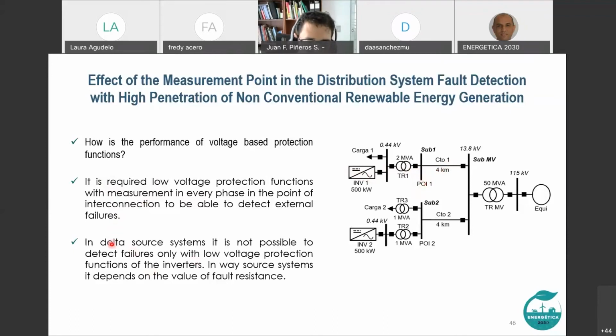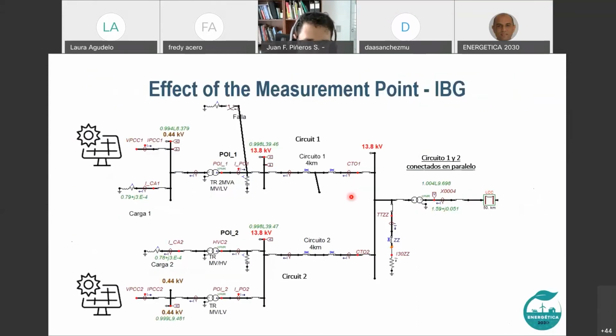And we observed that in delta source systems, when this transformer is in delta, it is not possible to detect failures, for example single-phase failures, with low voltage protection at the level of the inverter. If you have a delta connection, the low voltage protection function will not work properly. And if you have a wye source system, meaning a wye connection winding, you will detect only faults really close to 0 ohms. I will show you quickly.